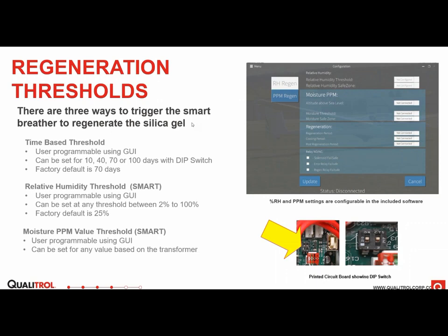So the regeneration threshold. As I mentioned, there are 3 ways to trigger the regeneration. Either time-based, you can do it through the relative humidity threshold, or we have a new feature, which is moisture parts per million in the desiccant chamber. And we'll talk a little bit more about moisture parts per million in the coming slides. But these are the 3 regeneration modes.